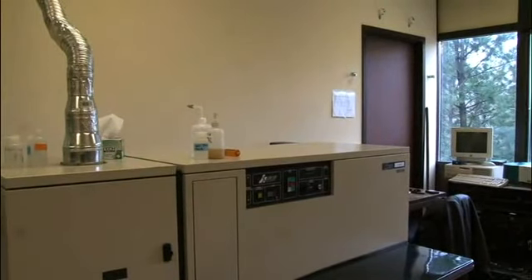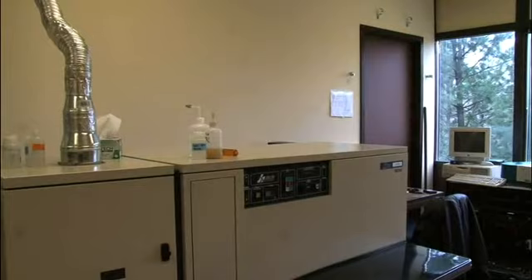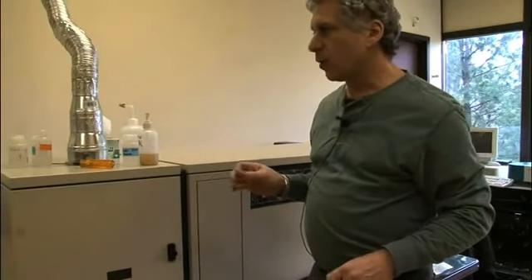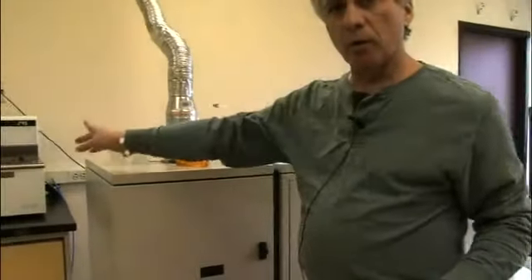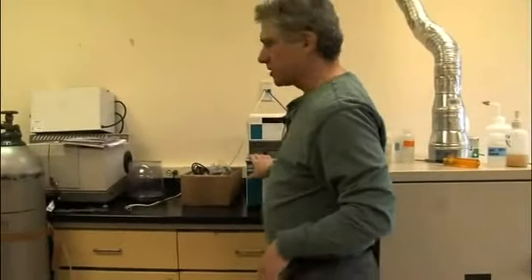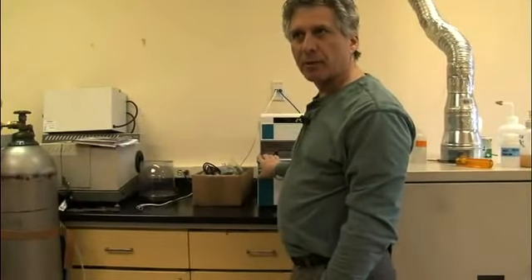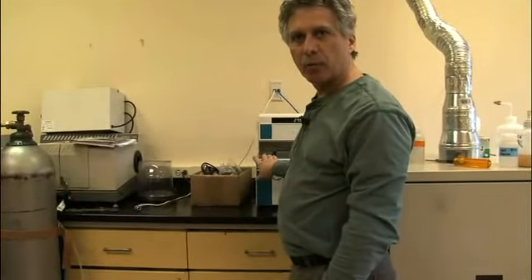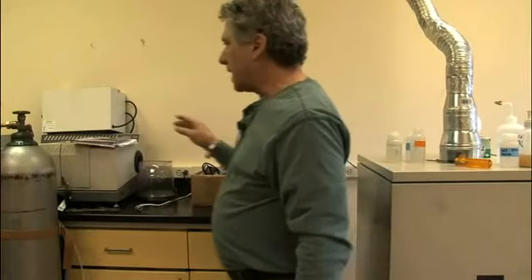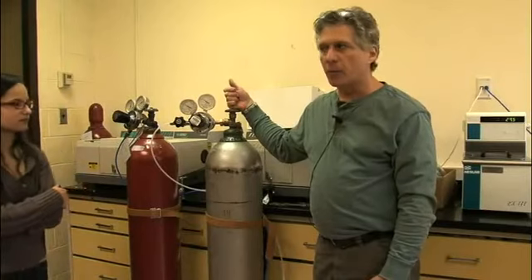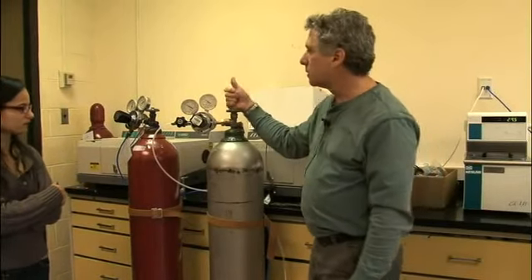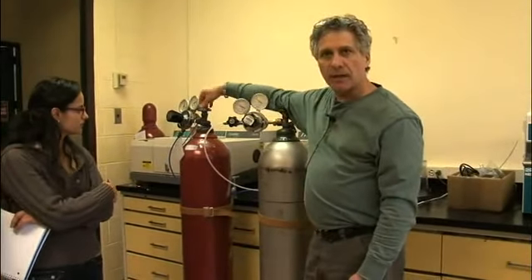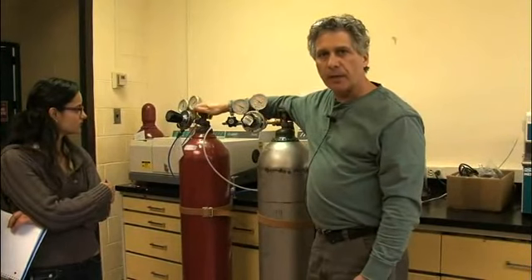Maybe this might work better. This requires cooling water over here, and this is just for recirculation, it doesn't have to be cooled. It's half tap, half DI water. The gases: argon, 4 nines purity is sufficient, pressure at 80 psi. Nitrogen, 4 nines again, 20 psi.